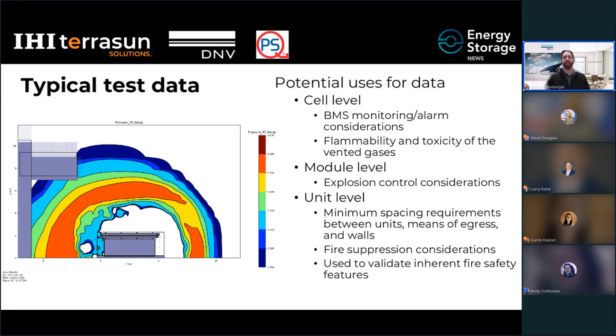So how can fire prevention be implemented in a BESS unit? First of all, there are 2 steps here. One is detection of an anomaly event, and the second is potential suppression of that event. So the first level of fire protection is at the cell level. The cell design will dictate the difference between those venting and thermal runaway temperatures that Carrie described. Now, typically, the larger the difference in these temperatures, the more time the protection system has to act and to potentially stop a thermal runaway event.